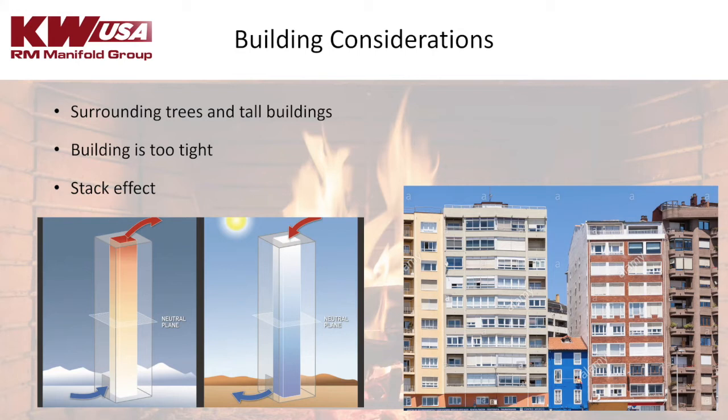So open fired systems often experience draft problems due to stack effect, because the chimney draft is eliminated due to negative pressure at the inlet of the heating appliance, which causes spillage into the room. So a lot of times, installing a mechanical draft system is the simplest, most effective, and least expensive option to fix a lot of these problems.